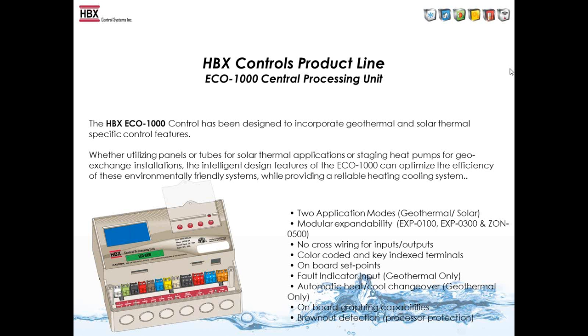Everything is the same as far as color-coded and keyed terminals. It has extra set points, there's no cross wiring, and you can use all of the expansion modules except for the Mod 100 because you don't do any modulating with an ECO. It has fault indicator, automatic heat-cool changeover.